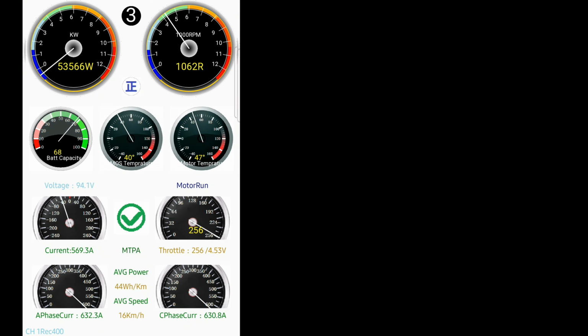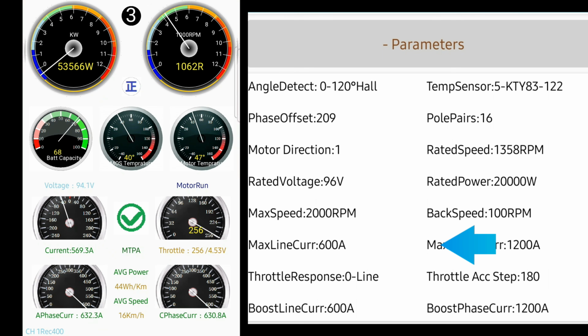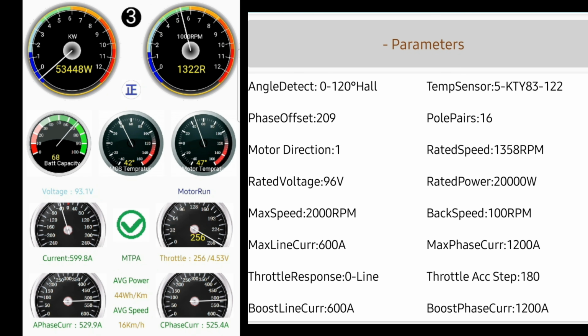So I've got several options here. I can limit the line amps from 600 down to control that sag. As you see, I come up more. We get to 1125, sagging more, 93.5. To 1300 RPM, you can see I've sagged down 13.8 volts, and I'm pulling 599 line amps.